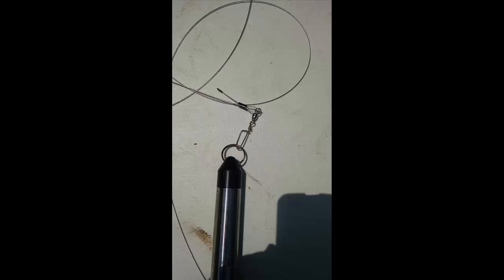When you take the water level logger out into the field to deploy it down a well, you'll need to either find or make a cable for hanging the logger in the well itself. So we have these cables here that we've made, which just use some metal wire fastened in a loop that's attached to some fishing swivels. In that way, we can attach one end to the ring on the water level logger and the other end to a ring that's attached at the top of the well itself. So all you need to do is hook up the logger to this cable and gently lower it down the well. Especially when you're lowering it below the water table, you want to slowly and carefully put this water level logger into the water itself so that you don't shock and damage the pressure transducer sensor.